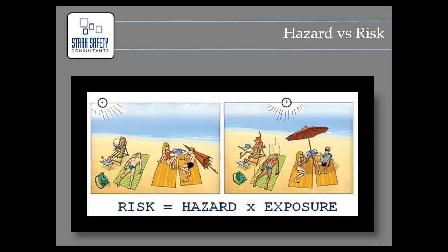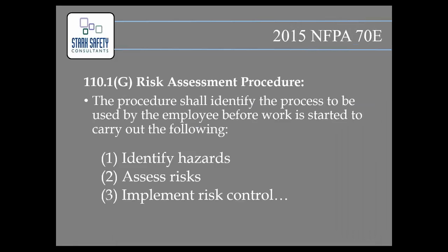I think this is a great visual to give us an understanding of the difference between hazard and risk. The hazard may be present at all times. It's based on your exposure to that hazard that determines the likelihood of the hazard injuring you or creating harm. So risk is hazard times exposure, and there are some formulas in the NFPA 70E Annex F as well as ANSI Z10 that can be used to help determine that risk assessment. So again, be very cautious: if you have an arc flash assessment completed without the risk, that may not necessarily be a completed process.